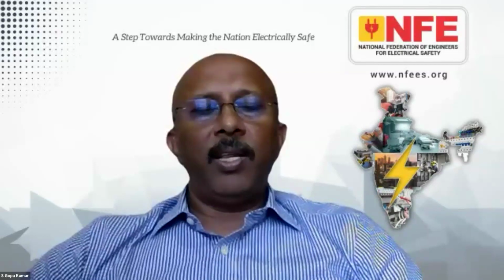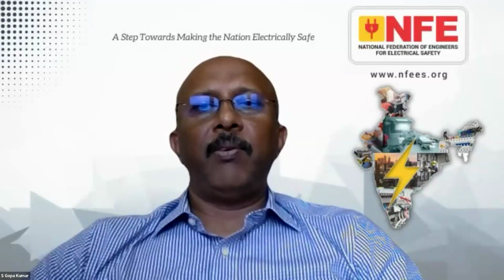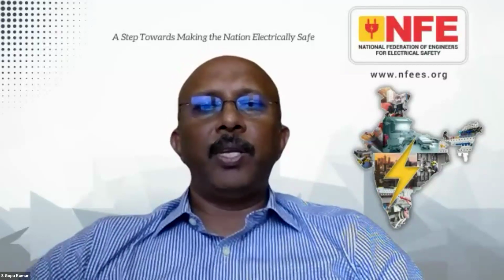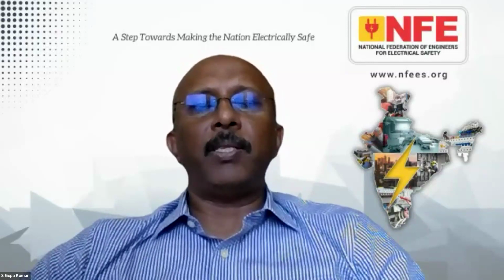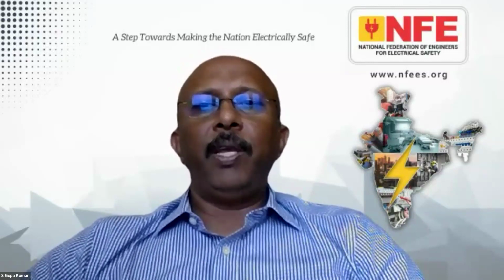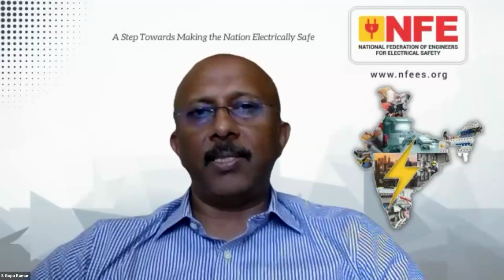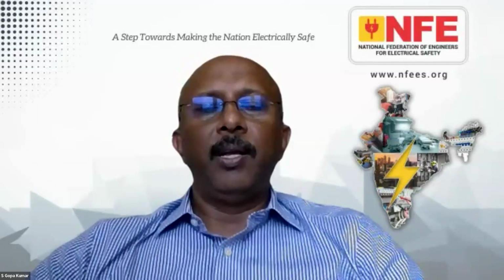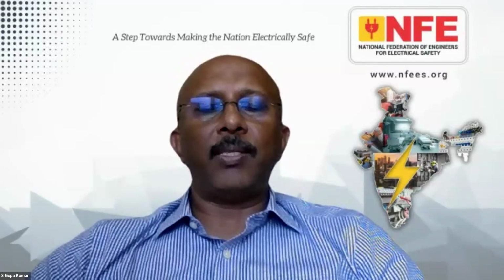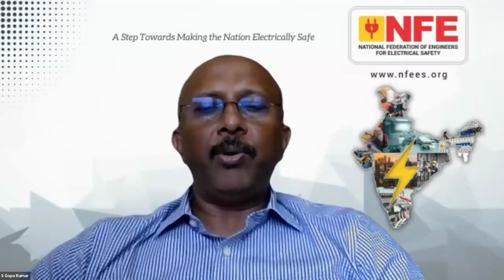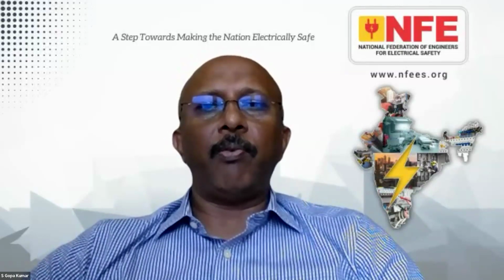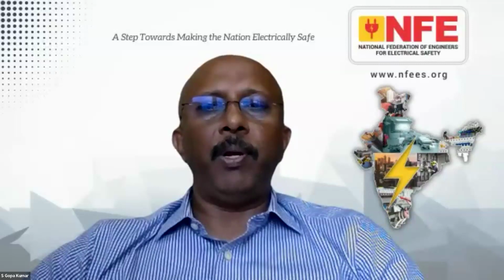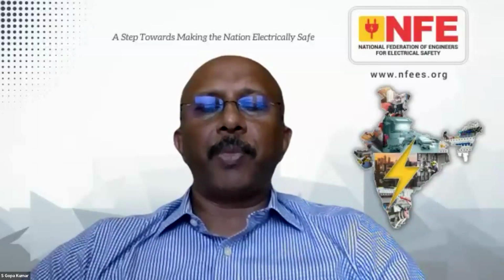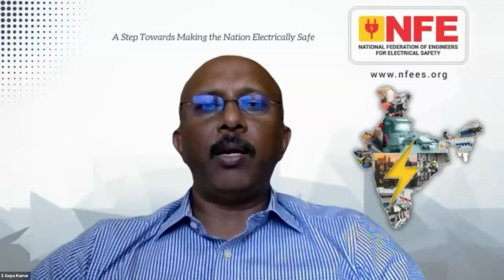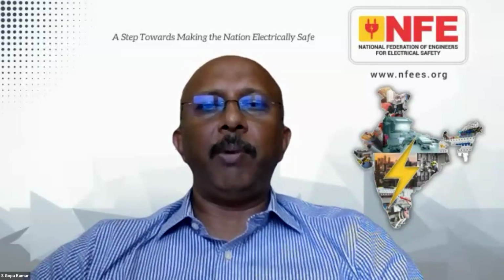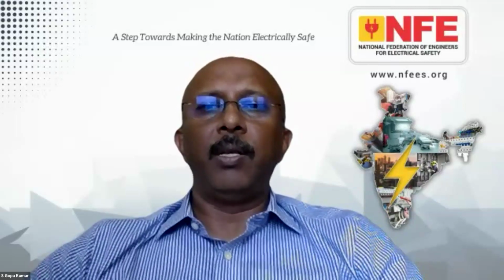Yeah, you see, whatever is written in the standard is the bare minimum. For example, the tables in the NEC or IEC 60364 Part 6 or IS 732, the tables and the verification are most suited for a small application, such as a residential application. But once we go to industrial applications, it is the skill of the engineer which decides what exactly has to be done. So the competent person should decide whether these tests are required or not. Of course, these are required, and the fault loop impedance or the line-to-line impedance you can calculate based on the available voltage and the fault current required to disconnect the device, and make a safety margin of 30%. You can very well calculate. These calculations are there in the standard.